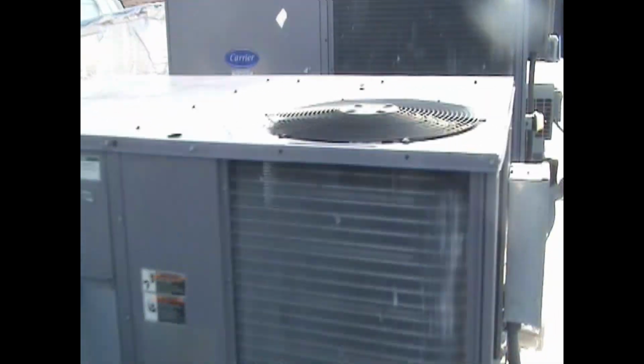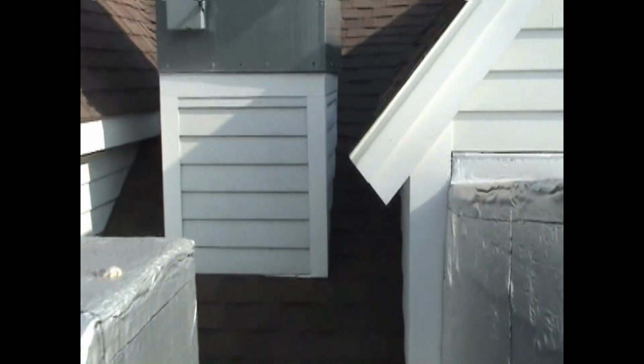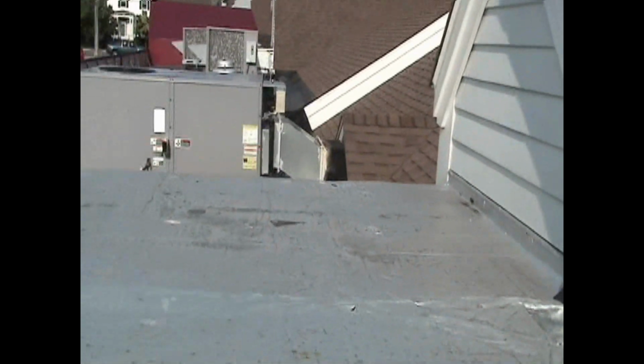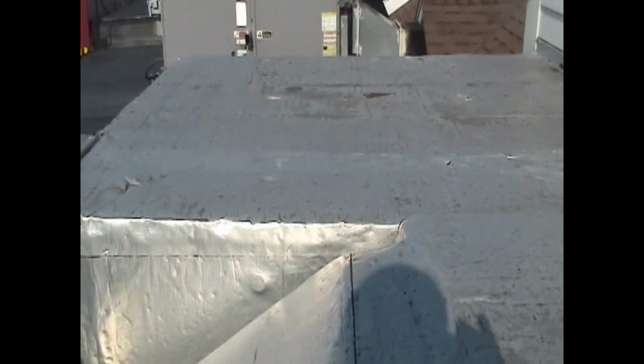So what you have over here is, I wanted to check to make sure that the condensate drains were draining. And basically I could tell by this that you had 2 different people do the units. You had somebody over here that was conscientious about somebody that has to work on this unit. As you can see, I have a little bit of a gap in here to get my hand in and clean out the drain if I need to.